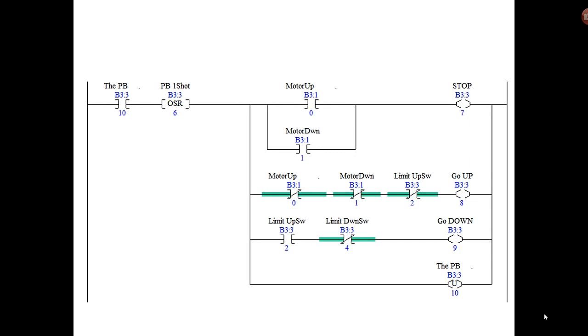And then the last branch is a bit of trickery, a little bit of magic—not when you think about it, it's not—but I'm using the unlatch bit to turn off the push button. Think about how you're going to use this. You're going to toggle B3:3/10, the push button. You don't really have a push button; you're going to use your mouse. You're going to mouse over B3:3/10 and you're going to right-click and then select toggle bit. When you do that, it turns on that bit in memory.